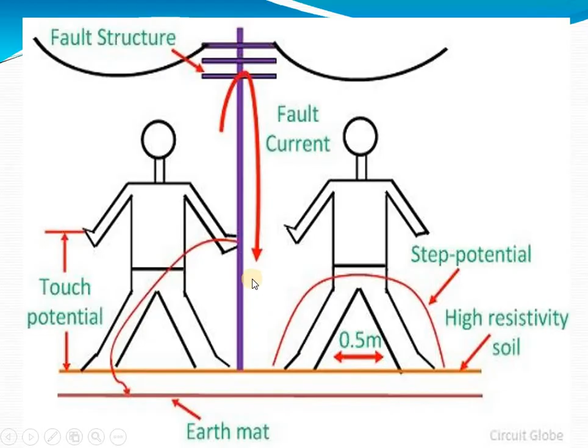This is touch potential: if a person touches a faulty element or a fault current is present and touches it mistakenly, a touch potential develops between that person's body and the ground. Now, if a fault current is present and the distance between the two feet is 0.5 meter, at one point there is a voltage at one level, and at the other point a different level, creating a potential difference, and the person might get a shock. This is called step potential.